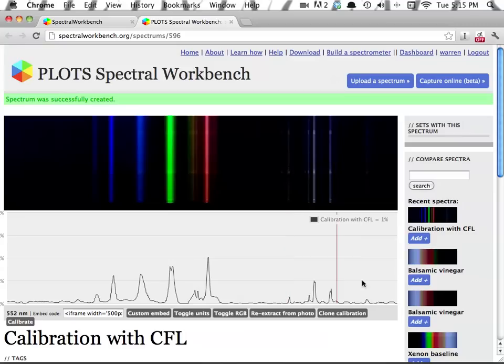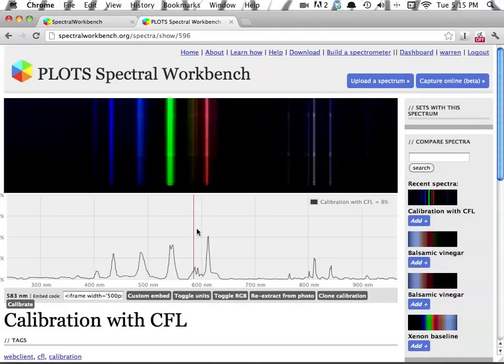And then we're going to try to clean up this interface and automate some things. But basically, you have to look down here and click calibrate. It could be on the other side, actually. It's wrapping. But it'll tell you to look for the middle blue band. There's three of them. So I'll click right there. And then the bright green band. Now, usually that's a single peak, but I think our reading isn't super good today. But once I've clicked, it reloads the page, and it's actually done the calibration.